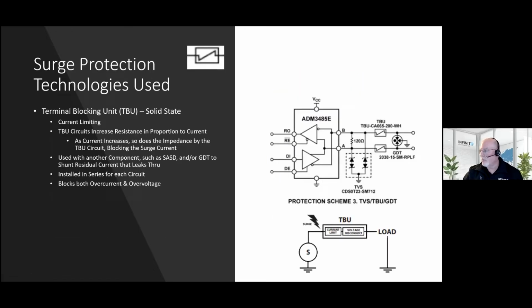Okay, this is kind of cool. We don't use this in everything, but we have some products that do. It's a blocking unit. And what it does is there's a circuit here, schematic symbol, that as current rises, so does impedance. The more current that's flowing through it, the more impedance it creates here. So when current wants to make that least path of resistance to ground, and it sees this here, it's seeing more and more resistance. It doesn't like it, so it wants to go somewhere else. But you don't want to just trust that. So we always add a gas tube here along with it to handle any residual surge currents that get through it. TBU stands for transient blocking unit.